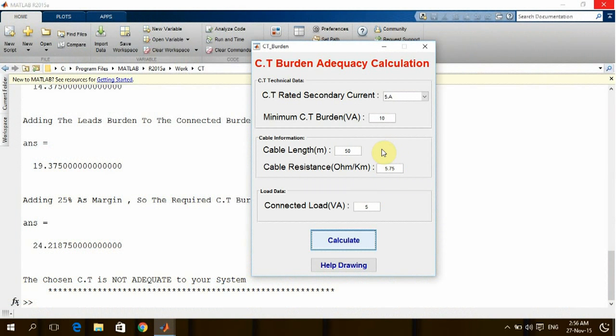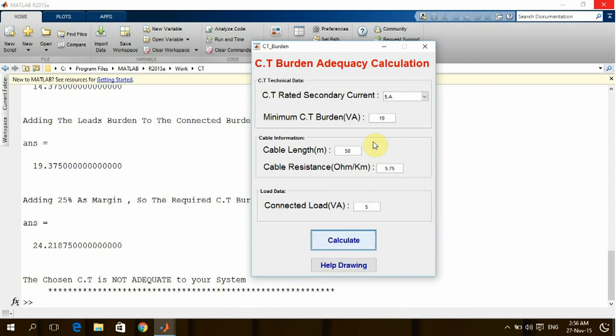In this case, the design engineer—since the connected load related to the relay is something he cannot play on it, for example changing the type or the manufacturer of the protection relay—has two parameters with which he can start manipulating one by one.